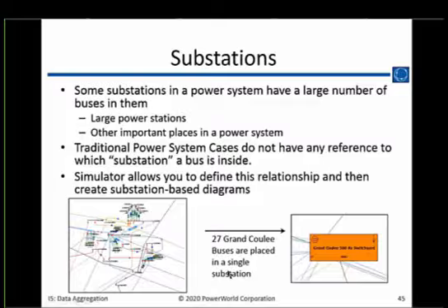So next up is substations. It used to be like the key reason why you'd want to use them is to kind of clean up a one-line diagram visually. But they're also very useful for other types of analysis. In the past several years, we've added geomagnetic induced current analysis, and those actually use parameters that are in the substation, like the grounding resistance, and the geography of the substation is kind of critical in that analysis. So it's taken on a new significance from what it's always had.